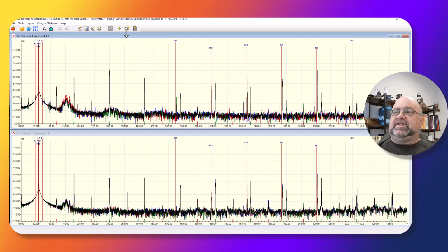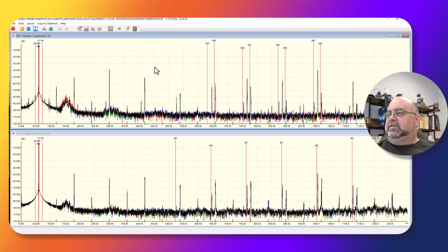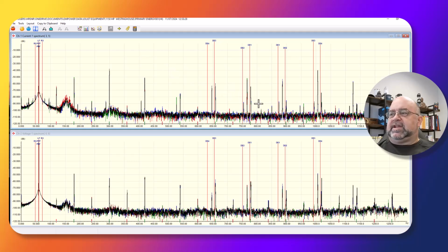Let's see, and then I can take a look at dynamic eccentricity. It's possible that it's got a little bit of orbit. Yep, definitely a little bit of orbit. So I have the peaks there, it's shifted a little bit. Some of that, because this is taken with CTs, especially if they're older CTs, some of the shifting I'm seeing, it could be a little bit of drift as we go out.